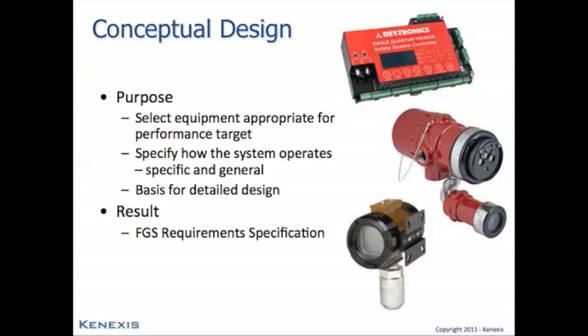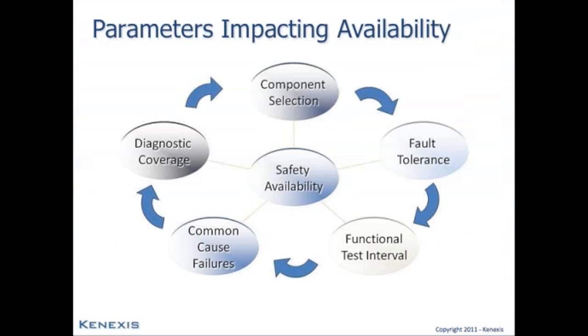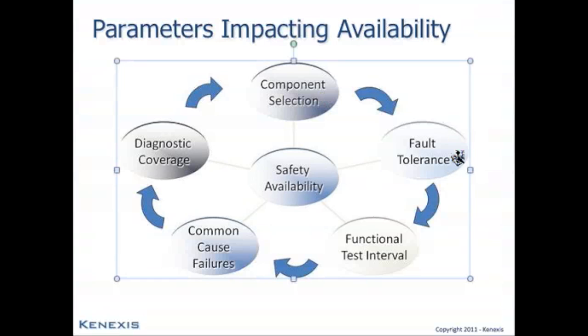Now, each of those FGS functions is going to be required to achieve a safety availability target. And there are multiple parameters that affect a function's ability to achieve its safety availability target. Those attributes include component selection, fault tolerance, functional test interval, the effect of common cause failures, and the diagnostic coverage of the devices in the loop. All of these items are factored into the calculations that verify whether or not an appropriate safety availability has been achieved.